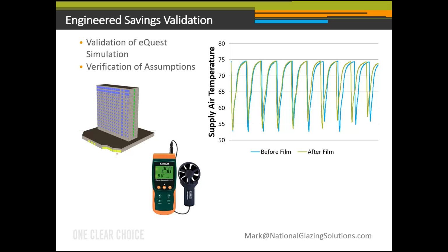Although we can perform the ESV on a PTAC power supply, chilled water temperatures and flow rate, or using your building's own EMS. In this case, with a constant volume fixed flow fan coil, we just used a data logging anemometer. Once installed, the data shows supply air temperature over time, and from supply air temperature we can calculate runtime, and from runtime we can calculate improvement.